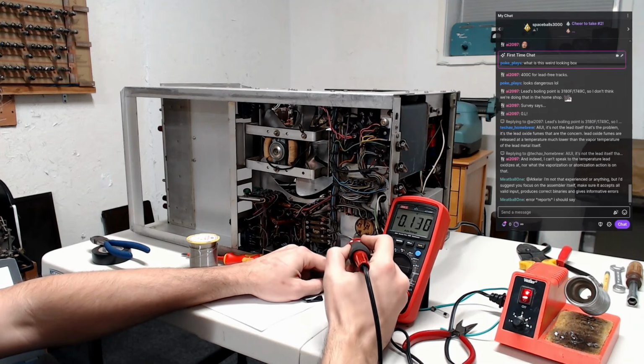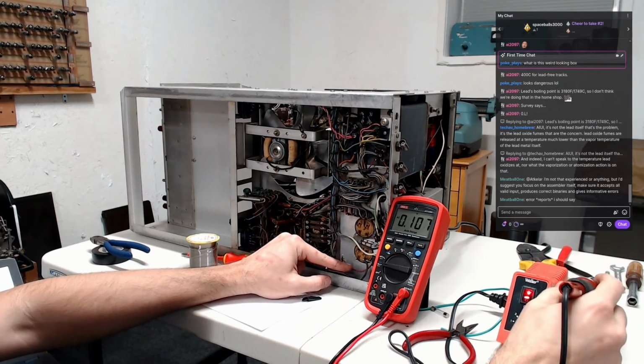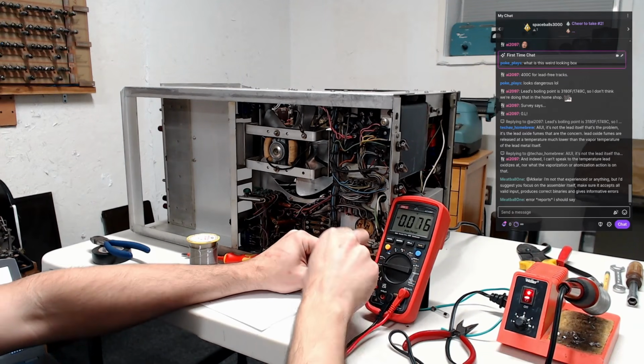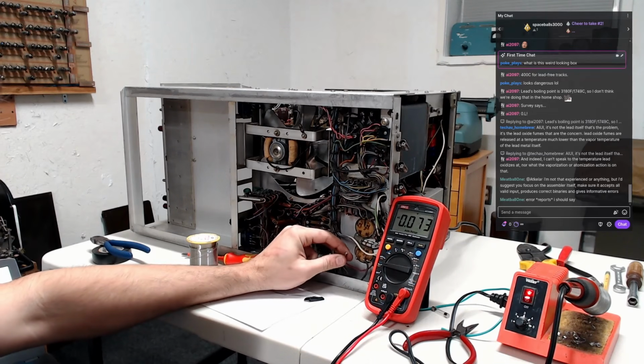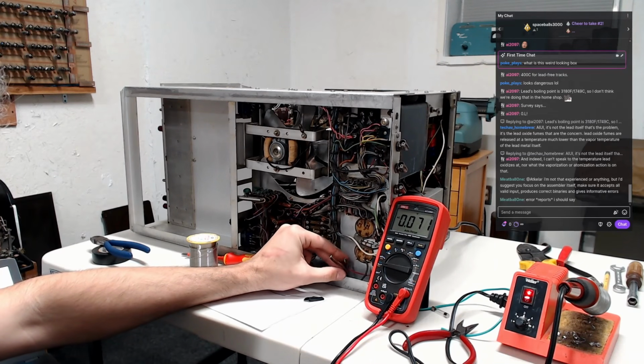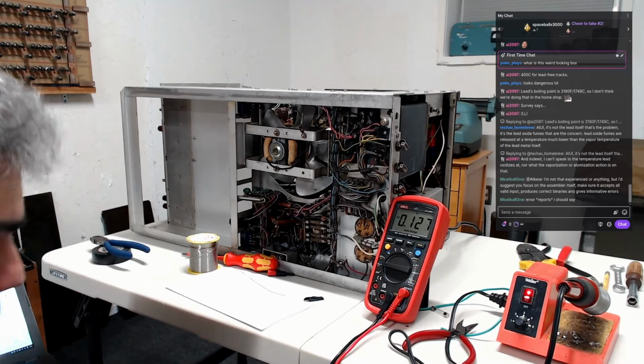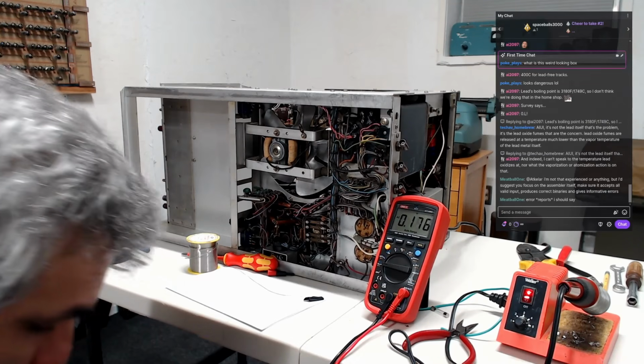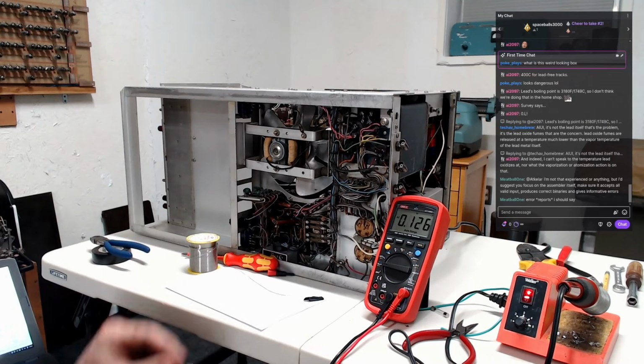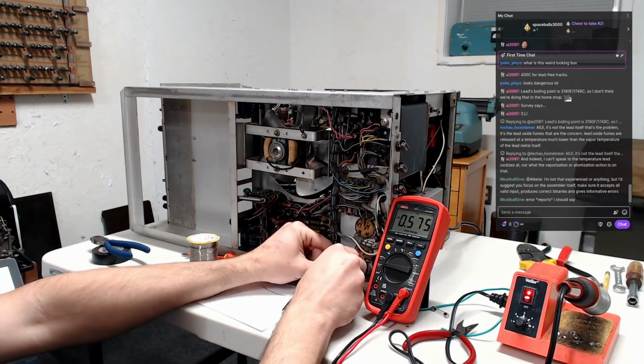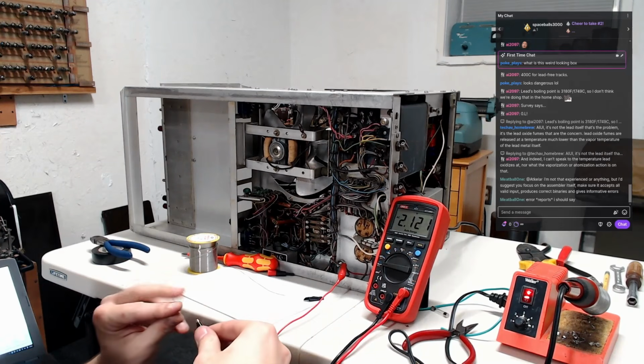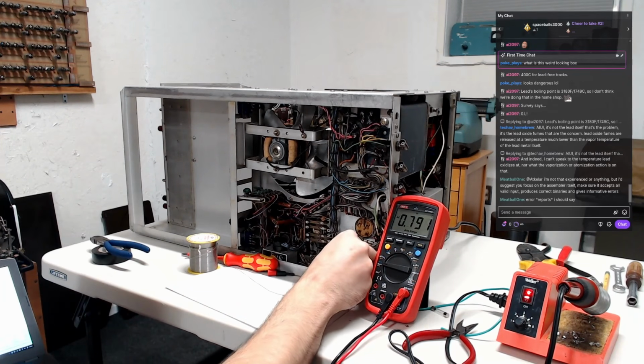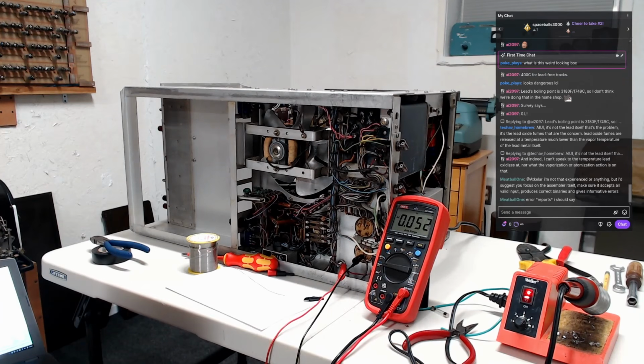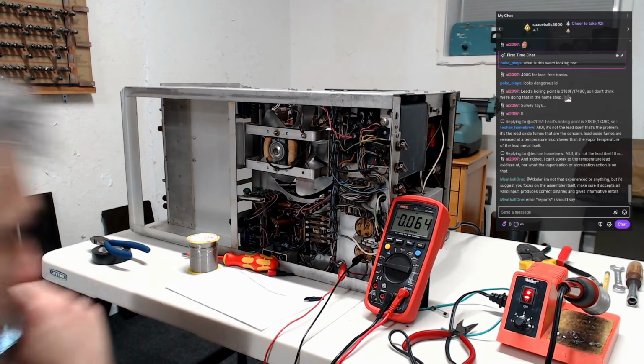You're still thinking it's a primary side thing? Yeah, this will isolate it. Right now this is AC, and both transformers are completely disconnected. That's the point of disconnecting the secondaries — if it still blows, you know it's a primary problem. If not, we connect one secondary at a time to find out which one is causing it.